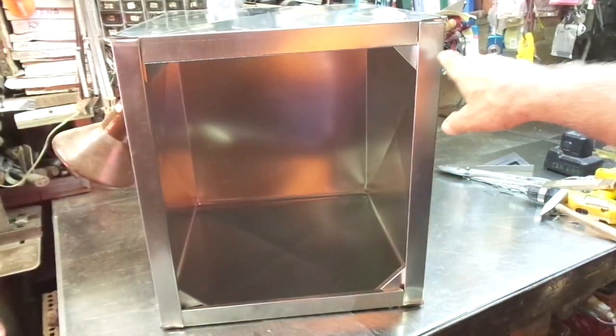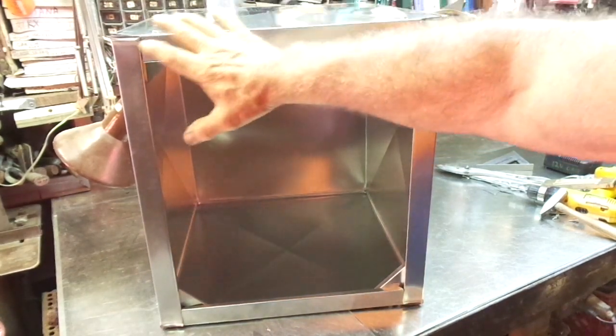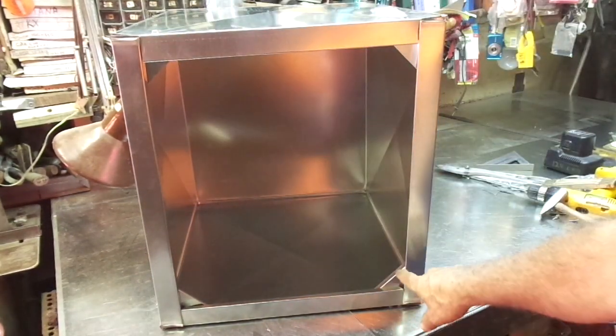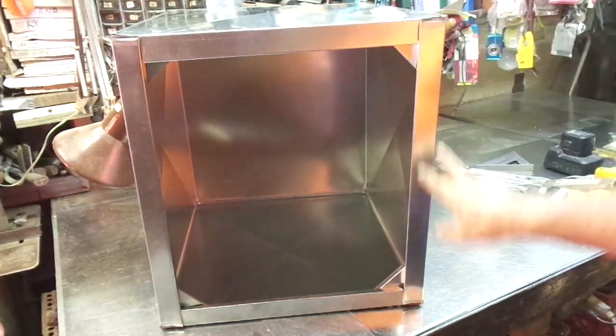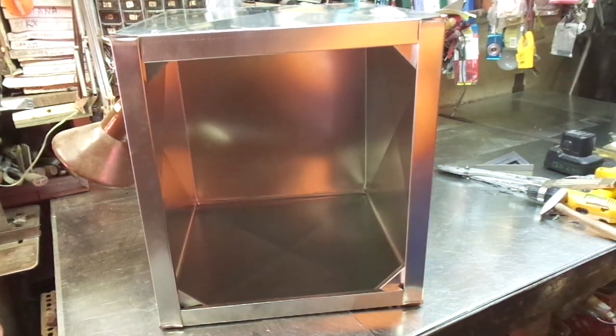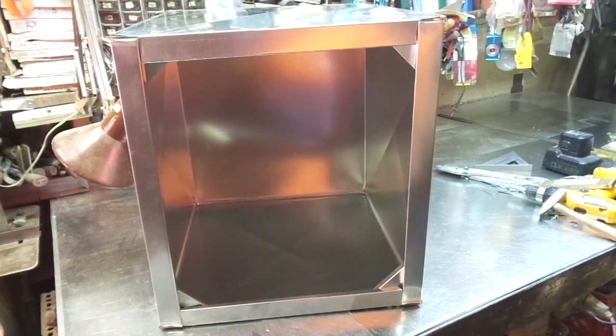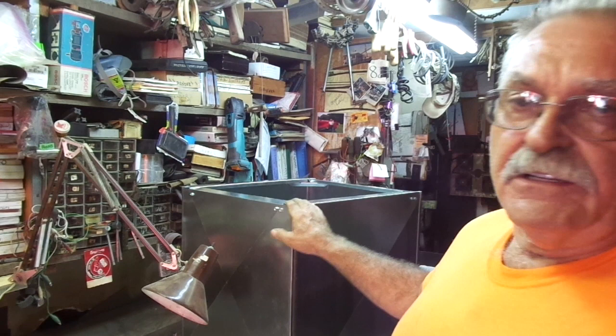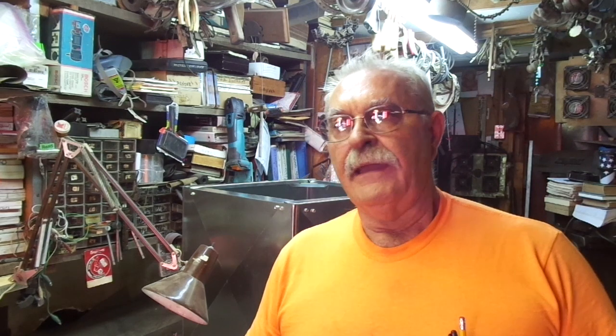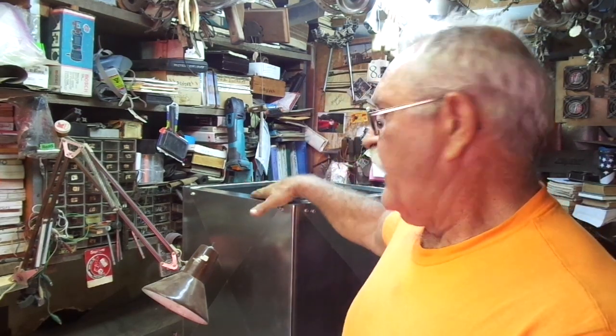What I'm going to do is I'm going to hold these right up inside here, pull everything down nice and square and put a screw in from the outside and have everything nice and secure. It's not going to wobble and it's going to have a lot more strength to support that furnace. And it doesn't take anything but scrap and about 10 extra minutes to do. There's the finished product. You can see it's nice and sturdy. It's not going to rack. It's not going to move with the weight of the furnace. It's held nice and securely. We'll take ArmaFlex tape and we'll put a seal of ArmaFlex tape around that, set the furnace on top. It should be just fine and dandy. I checked the dimensions with the ruler. It's supposed to be 22 inch by 19 and 3 quarter by 21 and a half. And it's within a sixteenth of an inch all dimensions.